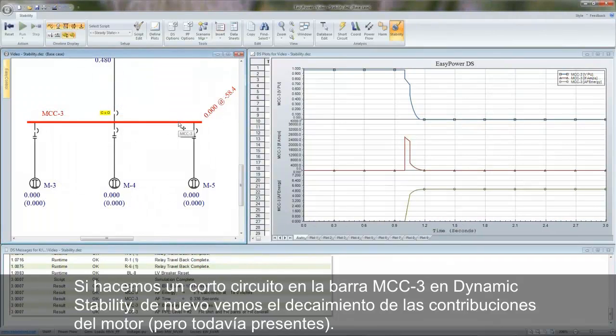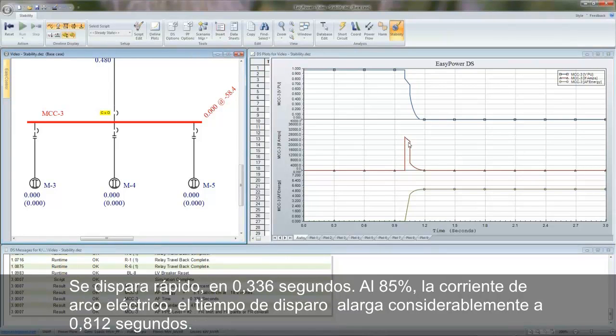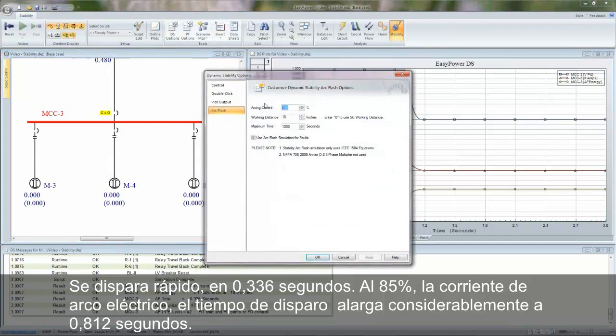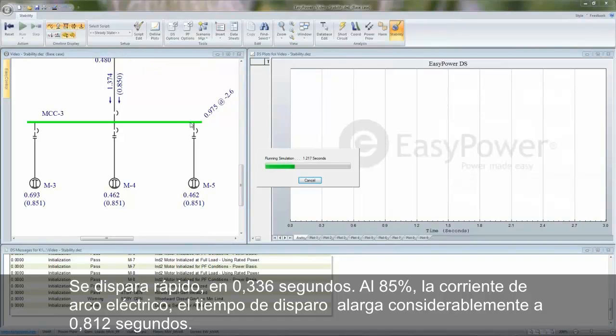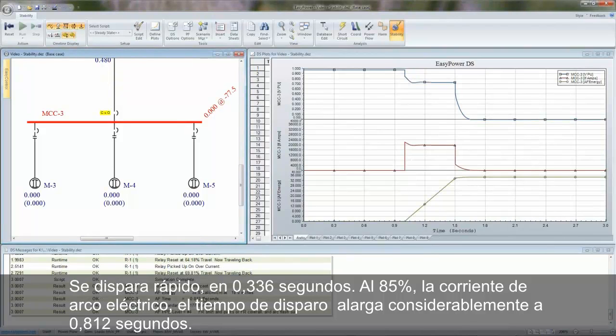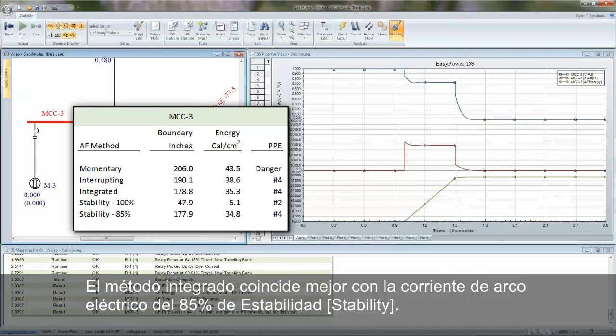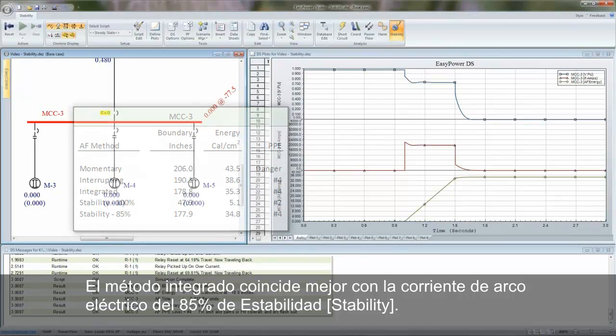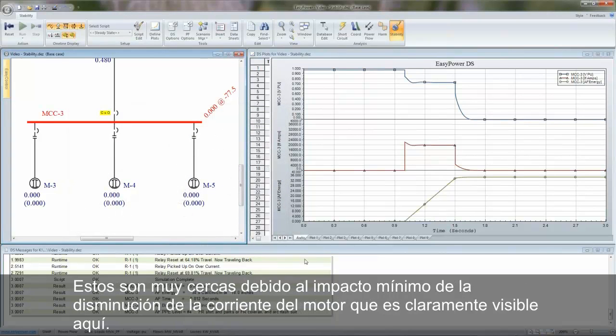If we fault bus MCC3 in dynamic stability, again we see the lesser but still present decay of the motor contribution. We trip quickly in 0.336 seconds. At 85% arc flash current, the fault time lengthens considerably to 0.812 seconds. The integrated method matches the 85% arc flash current in stability the best. These are very close due to the minimal impact of the motor current decay, which is clearly visible here.